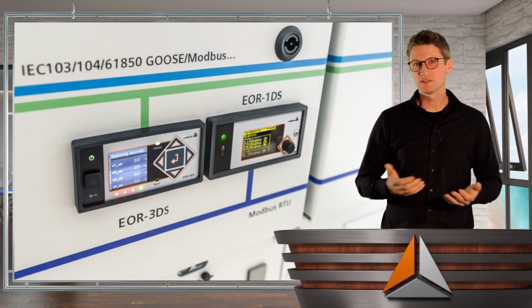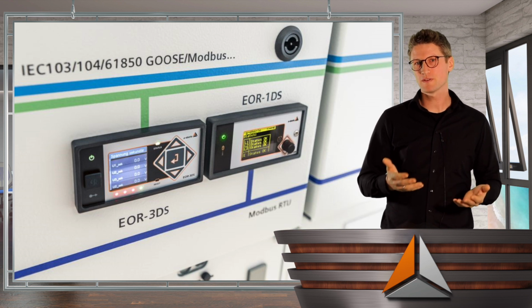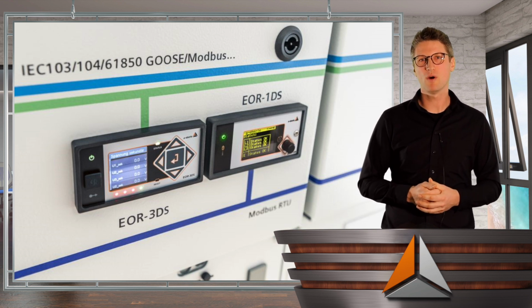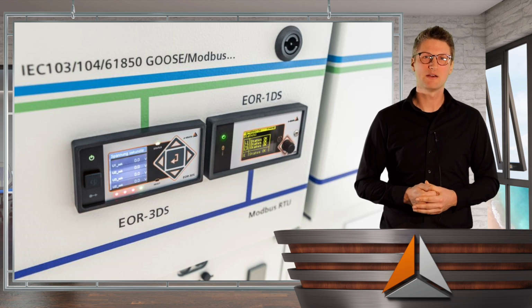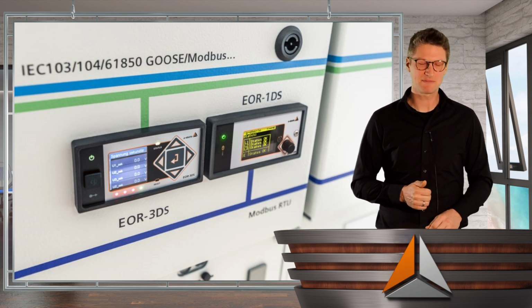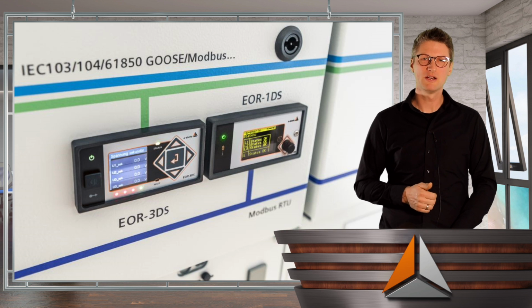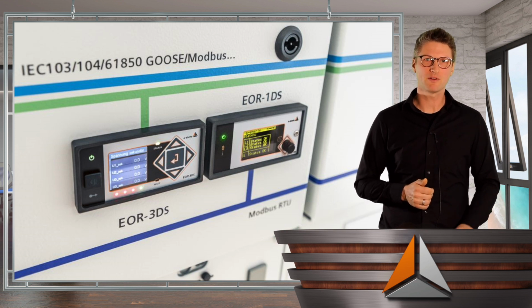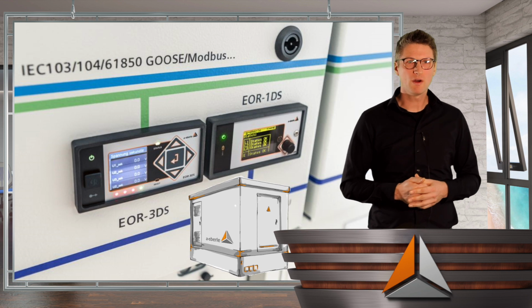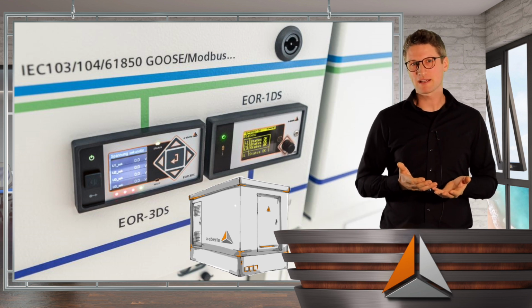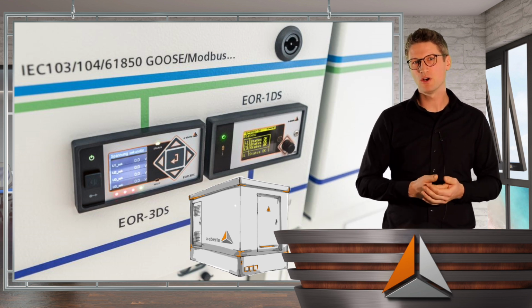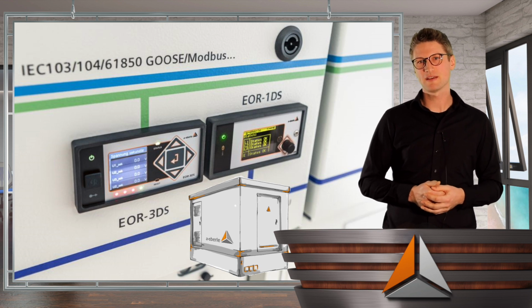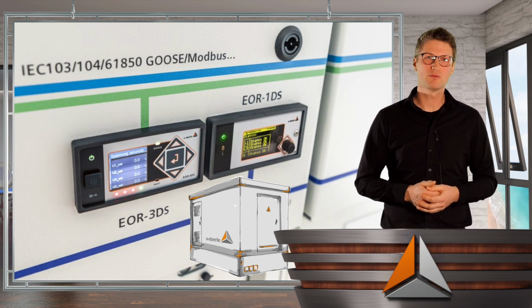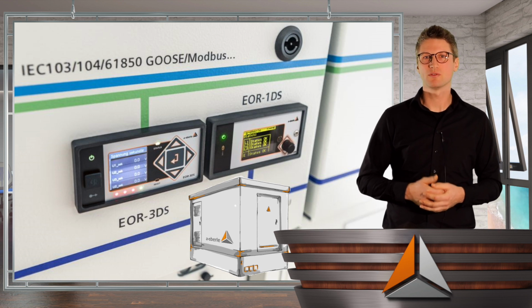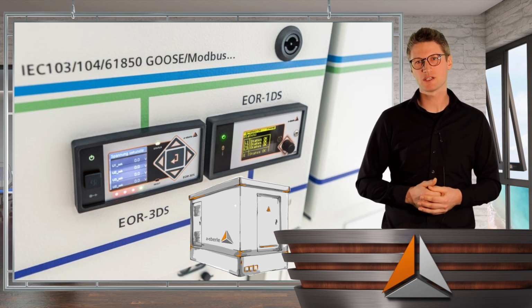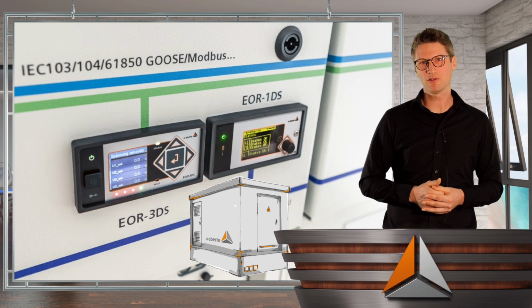Yeah, how to solve this situation? At first, I want to present our EOR1DS earth fault detection relay for simple secondary substations without remote control for additional monitoring in the depths of the grid. What are the key facts of simple secondary substations? They have often no SCADA communication to the central SCADA system. They are not remotely controlled. So somebody has to go there and switch in and switch off the cable fields.